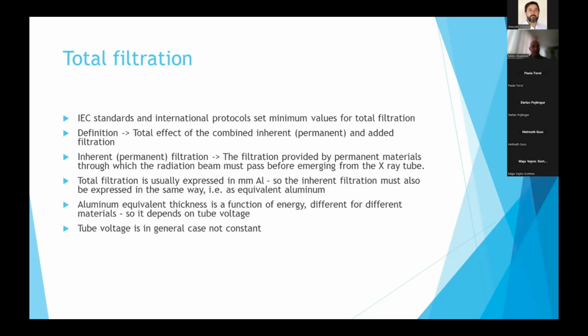First, of course, there is no primary standard for total filtration. There is currently no traceability. It is not possible to establish traceability for non-invasive total filtration measurements. Also, there are many different materials between the focus of the X-ray tube and the detector or the patient. There is the tube window, there are different filters, there is air, there is probably some cooling liquid. And again, you want to express total filtration as one number, so you cannot put thicknesses of all these different materials.